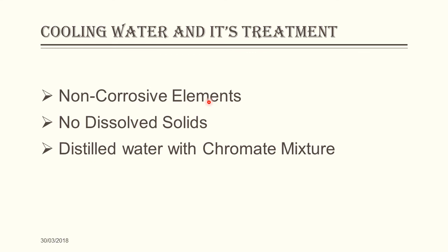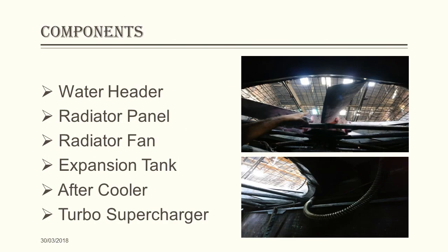Water is changed if hardness and chloride content is higher than the recommended limit. Therefore, fresh distilled water with chromate mixture is filled in the locomotive. The various components of the water cooling system are the water header, radiator panel, radiator fan, expansion tank, after cooler and turbo supercharger.